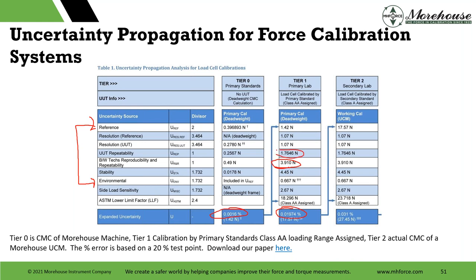UUT repeatability is going to come down. The other stuff is going to remain pretty much constant, unless you buy higher end meters or whatnot. But yeah, so you're getting around the 20% point without automation, around 0.02. With automation, I think the number that we showed, we dropped it to like 0.013 or something like that. And then you're going to calibrate something for somebody else, and that's where we get to this tier.